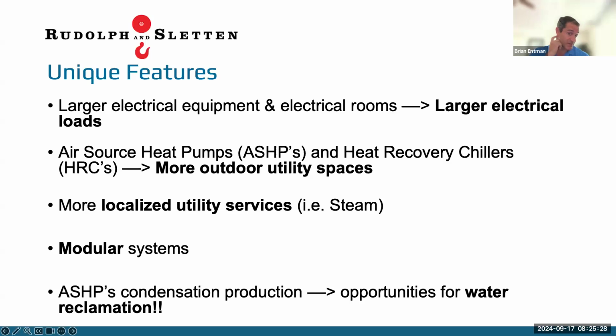As I mentioned, we're seeing a lot more localized utility services and elimination of mass steam distribution. For sterile processing, you'll have localized point-of-use steam distribution, and for humidification, more localized systems, eliminating the need for large steam systems that not only produce steam and waste heat but also serve heating demand—something that was costly to maintain.